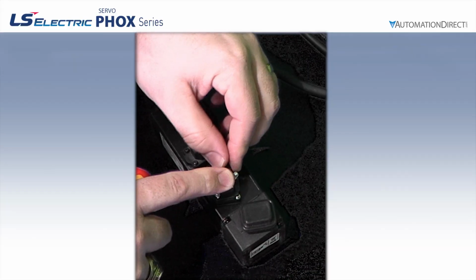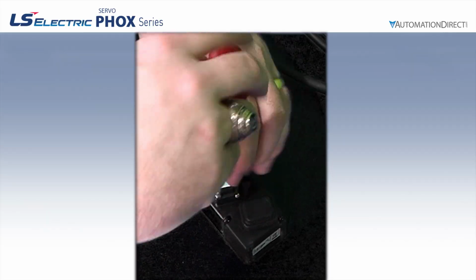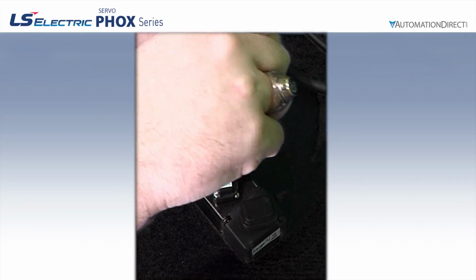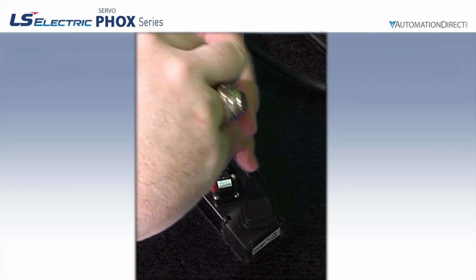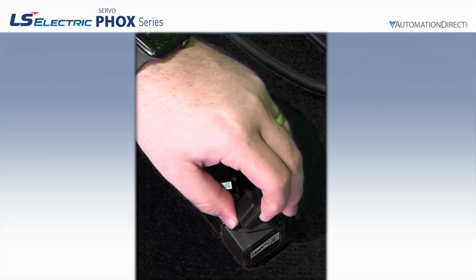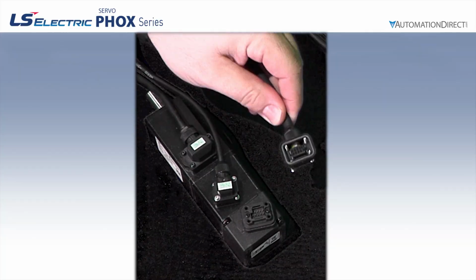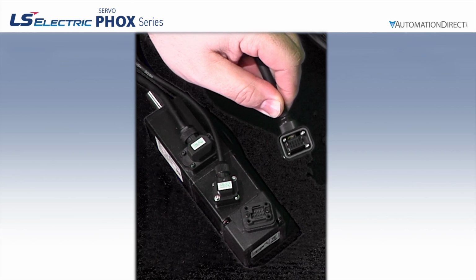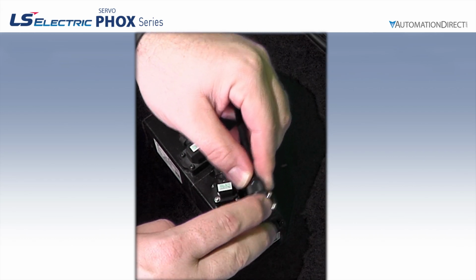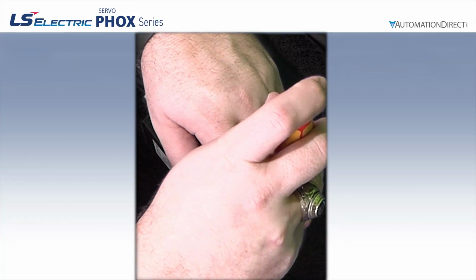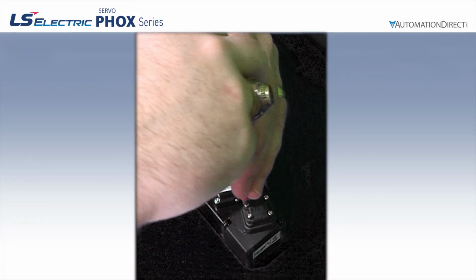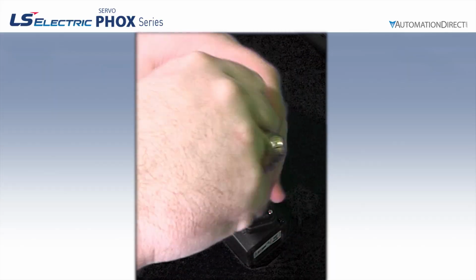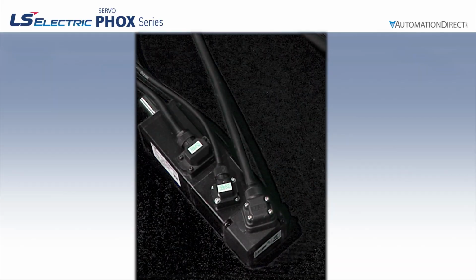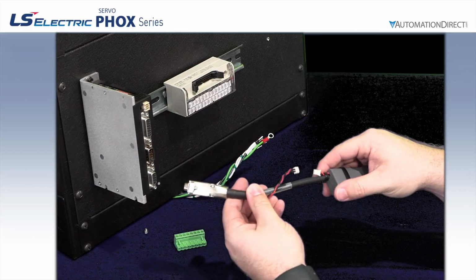This connector works almost identically to the motor power cable. Remove the rubber boot, confirm you are using the correct brake cable part number, and attach it in the only orientation available. Again, take care not to over-tighten the screws. And finally, we'll attach the encoder cable. Remove the rubber boot, then take the encoder cable and lightly press it onto the connector. It is keyed to install only one way, and you will notice a small cutout to assist with orientation. Press gently until it is fully seated, then tighten the 4 screws. Again, do not over-tighten.